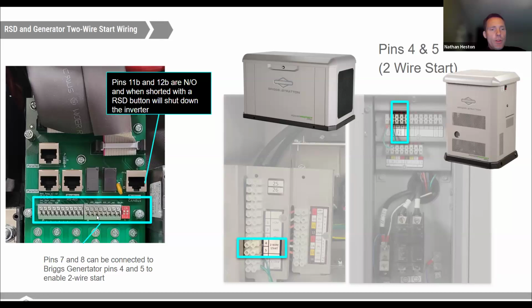And then pins 7 and 8 on the comms bar are used to do 2-wire start. So that's what allows the inverter to start and stop. It's a normally open dry contact. And so when it does call for a generator signal to start, it will close those dry contactors that will then create a continuous pathway through pins 4 and 5 on our generators. And so that's what will initiate your 2-wire signal to start. On the vertical, the wiring bay looks like this. On our horizontal generators, the wiring bay looks like this. Pins 11 and 12 here are also worth pointing out. That's your rapid shutdown button, or your rapid shutdown transmitter.